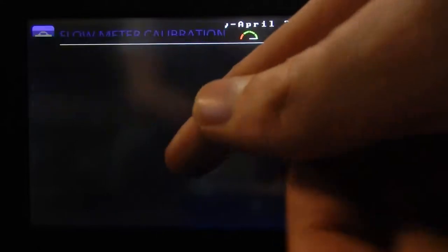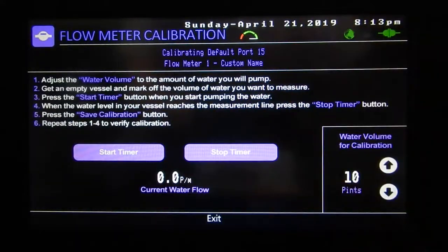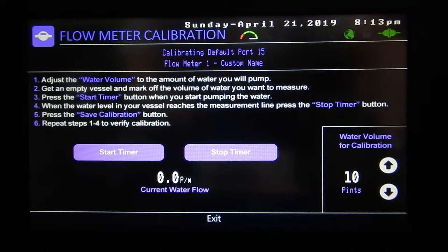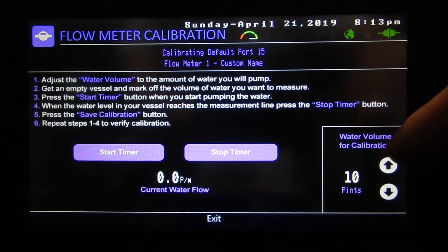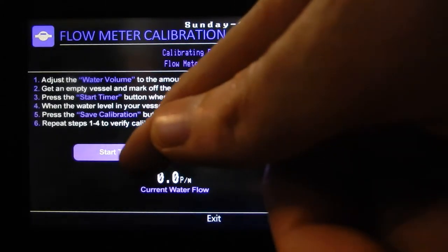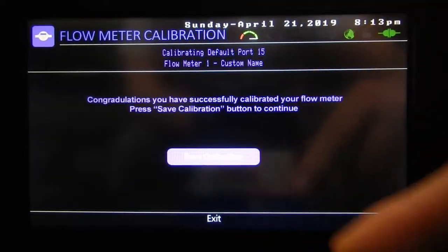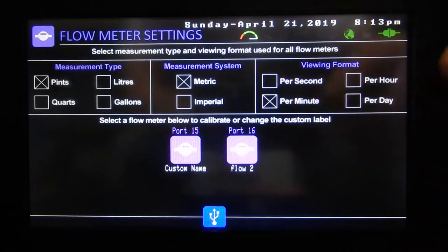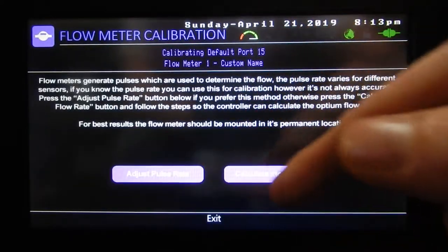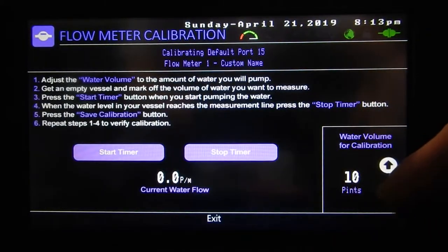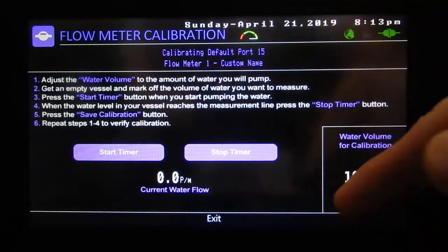Or we can do the better one: calculate flow rate. Now you're actually pumping water through here and there are instructions on how to do it — set the volume for calibration, start the timer, it'll start and stop, and now you've calibrated it. You're basically telling it how much water you're going to pump, then it times how long it took and figures out what the flow rate actually is.